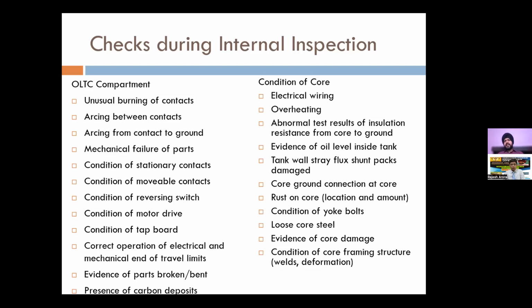Then OLTC compartment, if there is any unusual movement or any condition, stationary or movable contacts, then all that OLTC compartment also you need to verify. Then if there is any problem with the core, particularly any rusting is there, or you find some places the core is improperly moved. Recently there has been one incident where the core earthing, the core lamination earthing was not proper. The insulation was degraded, so it was causing circulating current inside the core. So all these things need to be recorded properly.